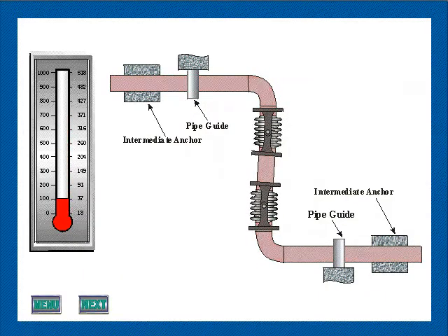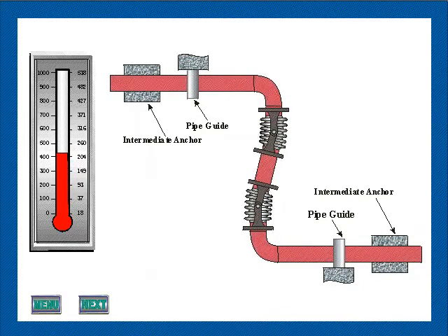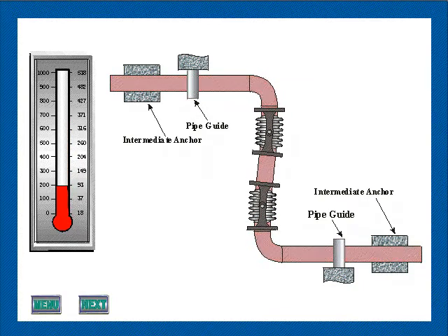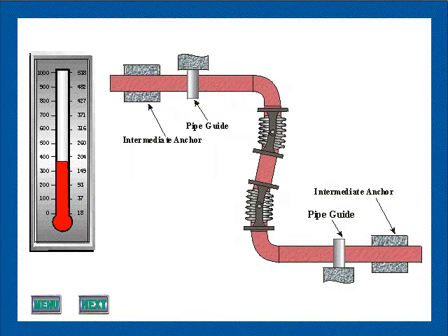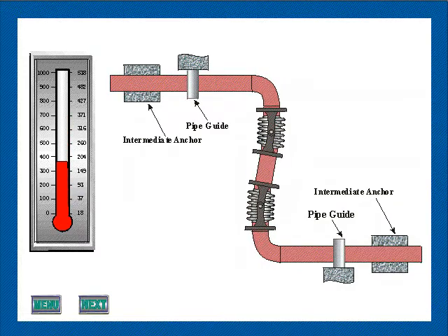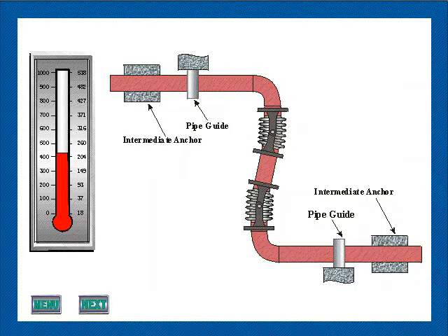This animation illustrates the use of a two hinge system to absorb the major thermal expansions in a single plane z-bend. Since the pressure thrust is absorbed by the hinges on the expansion joints, only intermediate anchors are required at each end of the piping system.